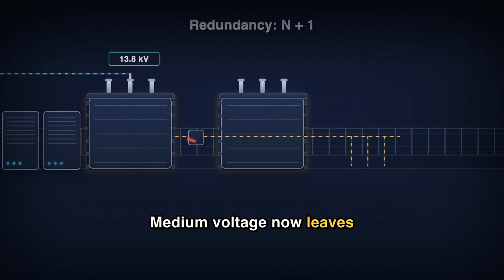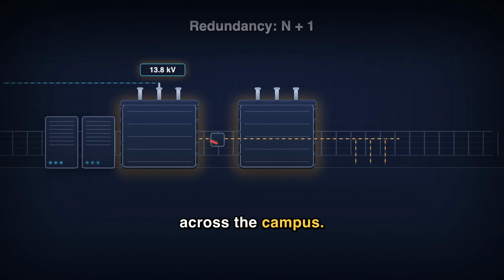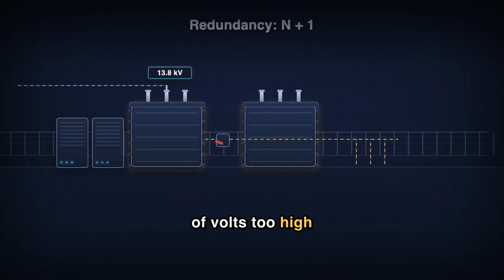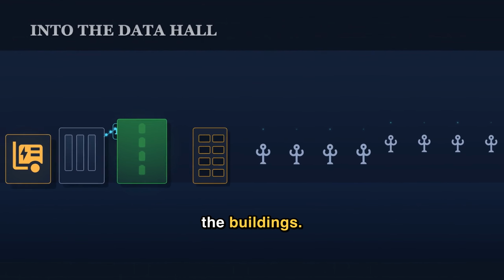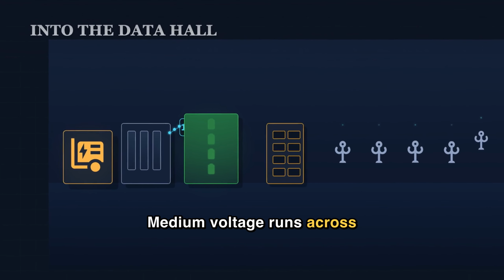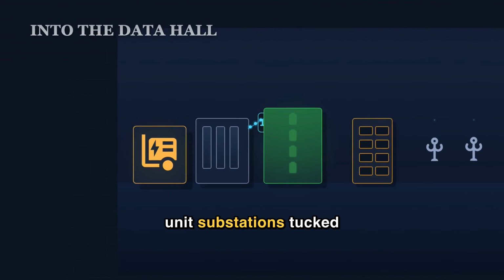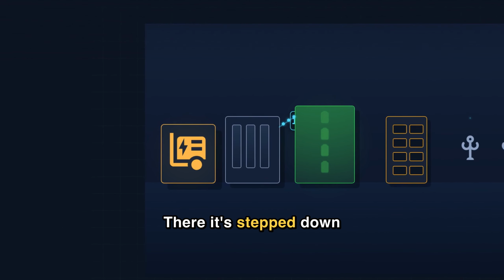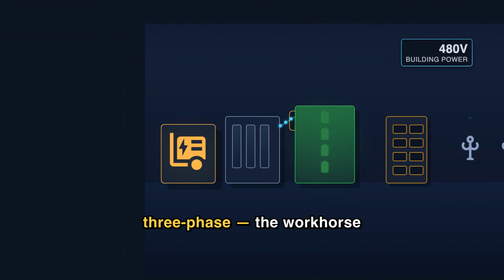Medium voltage now leaves the substation, fanning out across the campus. But it's still thousands of volts too high for a building. Follow the power into the buildings. Medium voltage runs across the campus to smaller unit substations tucked beside each data hall. There it's stepped down again to 480 volts 3-phase, the workhorse level that feeds the building's floor.